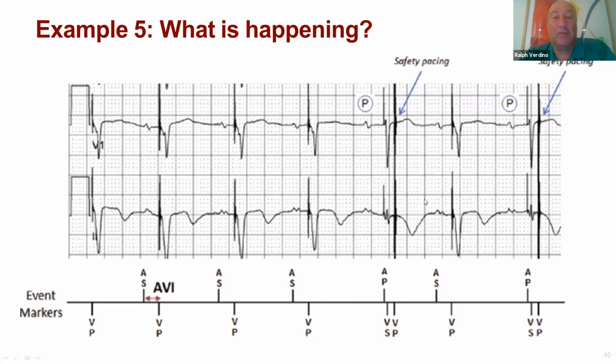And therefore, if it really was maybe that I'm just sensing the atrial spike or the atrial deflection in the ventricular channel, and in order to prevent there to have been asystole, I'm going to pace in the ventricle at a short delay, so I avoid pacing on the T as a regular programmed device, but I'm going to pace nevertheless.